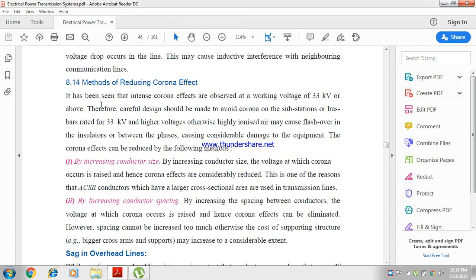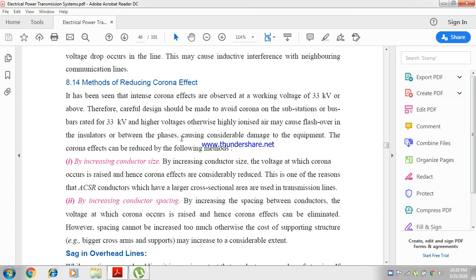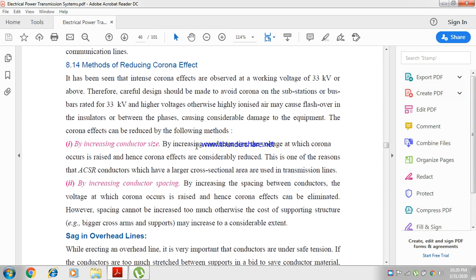Therefore, careful design has to be made to avoid corona on the substation or bus bars rated 33 kV and higher voltage. Otherwise, highly ionized air may cause flashover in the insulator or between phases, causing considerable damage to the equipment. The corona effect can be reduced by the following methods.